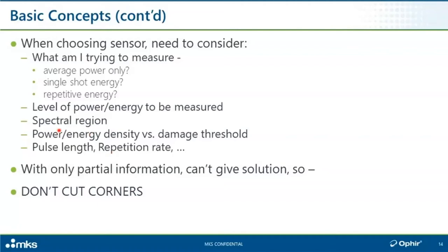What kind of power density or energy density is my sensor going to be exposed to? Can I control that? Even if my application involves focusing a beam to drill holes in aluminum or cut silicon wafers, do I need to place my sensor in the focal plane? Usually I don't. If I'm involved with a pulsed beam, what's the pulse length and repetition rate? All of these things affect my choice of sensor. If I cut corners and only consider partial information, I shouldn't be surprised if I choose a sensor that ends up not working or getting damaged.